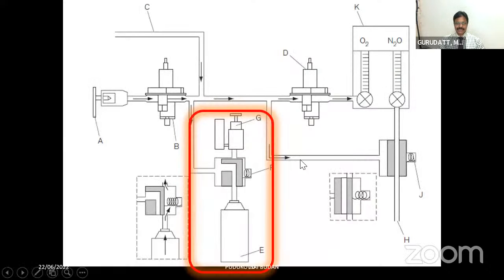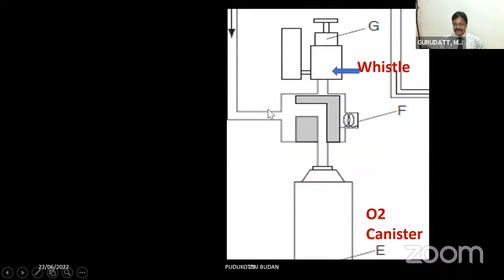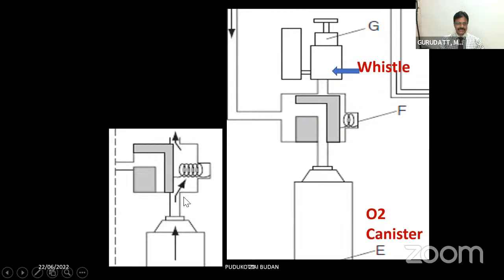I'll just show you a diagrammatic representation. So this is the canister I was talking to you about, and this canister is actually separated from the whistle by a seat and a spring. Because the pressure of oxygen flowing into the canister is high, it is pushing the seat and blocking the whistle from communicating with the oxygen source in the canister. Once the oxygen pressure falls, the spring pushes the seat away, and there is direct communication between the canister and the whistle, which will start blowing. So that's how, once the whistle starts blowing, you know that the oxygen pressure has come down to less than 30 psig, and then you will have to open a backup cylinder.